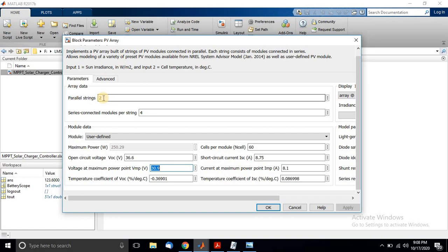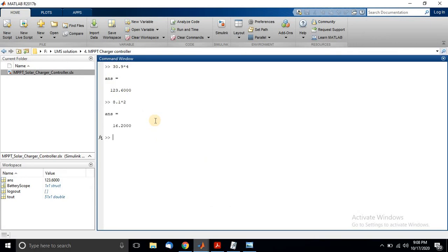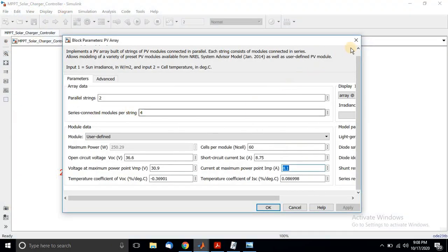With 2 parallel strings, you multiply the current: 8.1 × 2 = 16.2 A at maximum power point under standard test conditions. So the power of the PV array at maximum power point under standard test conditions is 123.6 × 16.2 ≈ 2000 watts. The array rating is 2000 watts consisting of 2 parallel strings and 4 series modules.